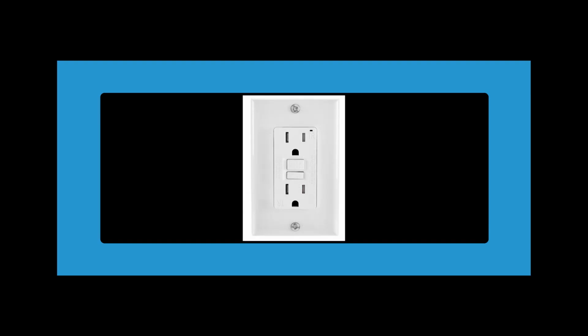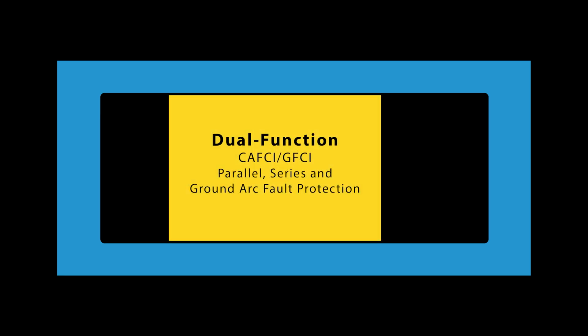So you may be wondering how these are different from GFCIs, or ground fault circuit interrupters. Well, while AFCIs and GFCIs might seem very similar, they serve very different purposes. GFCI protection is designed to protect from electrical shock by detecting ground faults, while AFCIs focus on preventing electrical fires by detecting arc faults. Some circuits may require both AFCI and GFCI protection, and there are combination breakers which provide both types of protection in a single device.